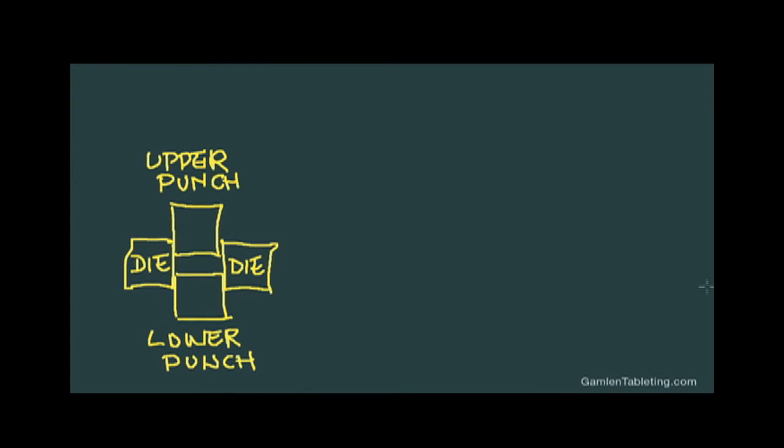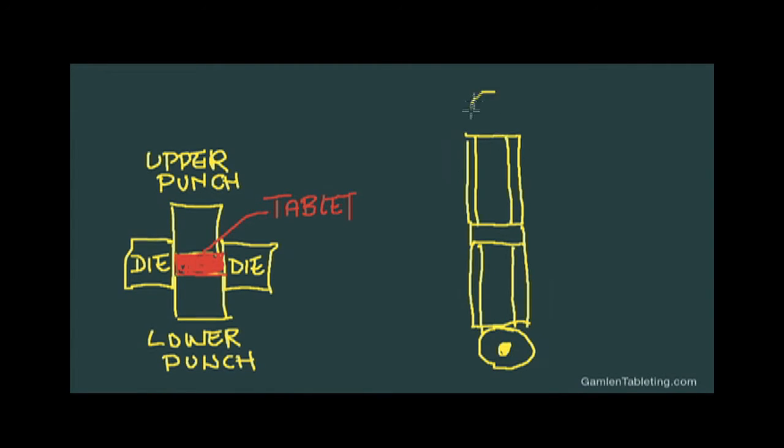Single punch and rotary presses work on a similar principle. They compress material to a particular thickness. On a single punch tablet press, thickness is determined by the upper punch position. On a rotary press, thickness is determined by the distance between the upper and lower compression rollers.